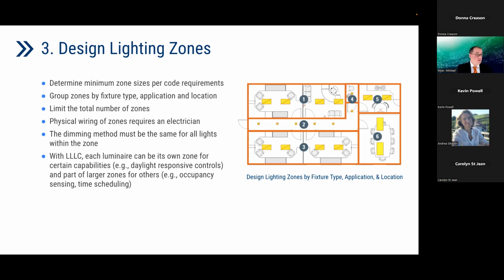One of the other challenges with zone design is how you are running the physical wires or connections to them. Some of these things can be done digitally through wireless controls and other means. Something to think about is luminaire level lighting controls, LLLC. The idea there is you're now putting a sensor, typically an occupancy sensor and probably a combined daylight sensor, in each fixture. And then most often you're also going to do some networking capability, even if it's on site. And there you can actually have different types of control design zones, or you could change them after the fact digitally through an on-site tablet or even an iPhone or a mobile phone kind of application where you can rezone certain spaces through that. And that's an advantage of luminaire level lighting controls.